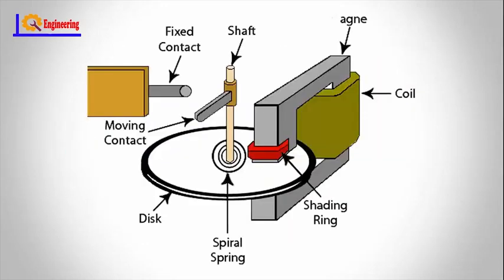Induction-type relays. These are used as protective relays in AC systems alone and are not usable with DC systems. The actuating force for contact movement is developed by a moving conductor that may be a disc or a cup through the interaction of electromagnetic fluxes due to fault currents. These are of several types like shaded pole, watt-hour, and induction cup structures and are mostly used as directional relays in power system protection and also for high-speed switching operation applications.